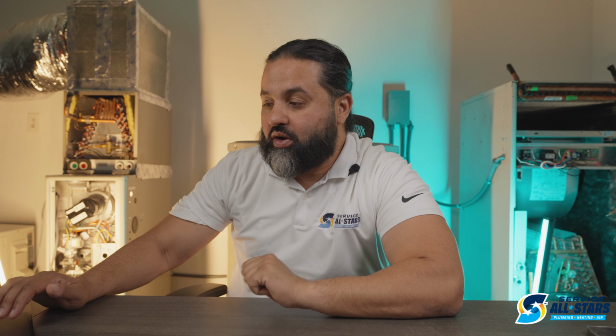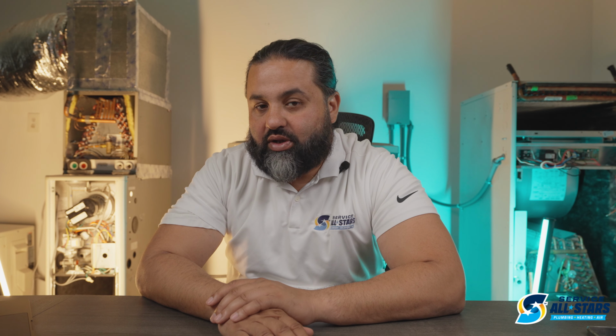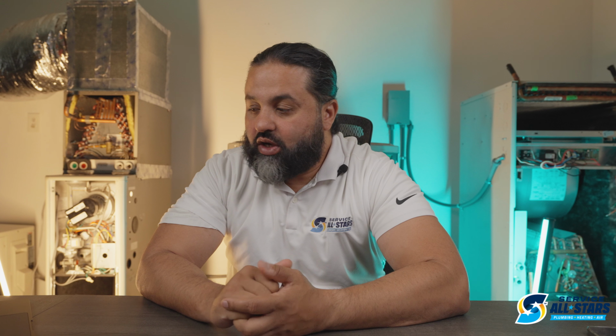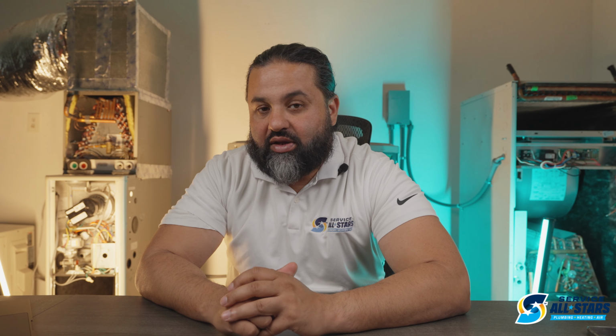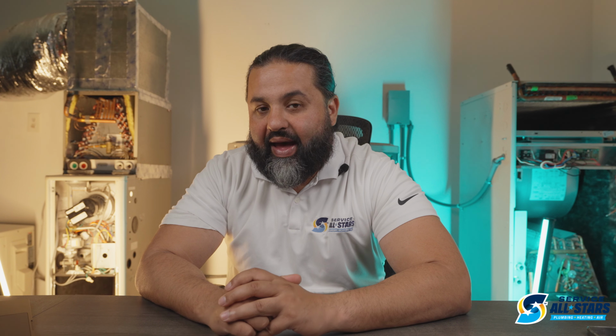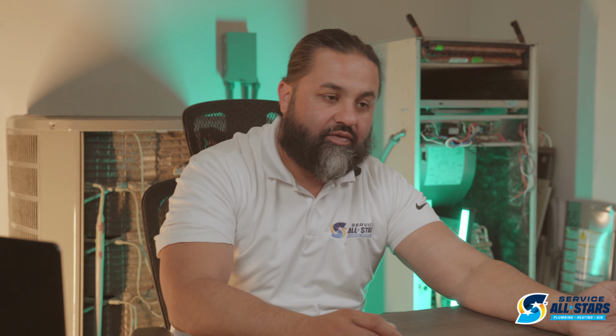So the system is going to work a lot longer, and because it's going to work a lot longer, there's going to be a lot more wear and tear on the parts, and that's going to cause higher repair costs, premature repair costs, or total replacement of the system very, very soon. So we have a lot of solutions for reducing the static pressure, and like I said, that's the first thing that our technicians focus on: how we can get the client's system to operate at the proper static pressure levels. Our technicians first take the static pressure of the return plenum and the supply plenum, and then we get the total static pressure reading as well.